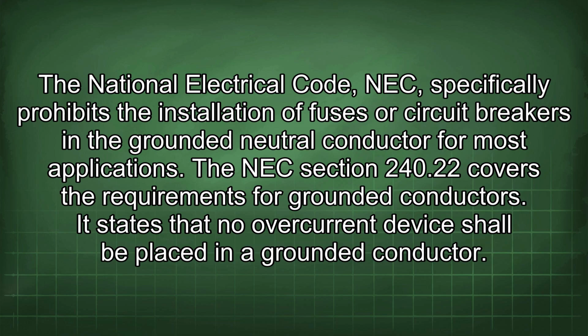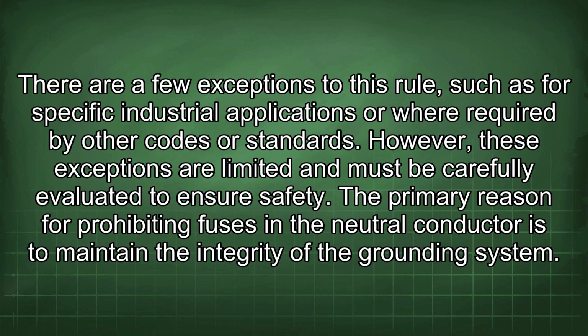The National Electrical Code, NEC, specifically prohibits the installation of fuses or circuit breakers in the grounded neutral conductor for most applications. NEC Section 240.22 covers the requirements for grounded conductors. It states that no overcurrent device shall be placed in a grounded conductor. There are a few exceptions to this rule, such as for specific industrial applications or where required by other codes or standards. However, these exceptions are limited and must be carefully evaluated to ensure safety.